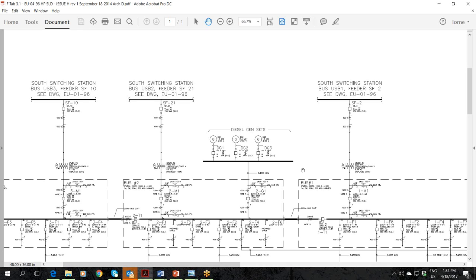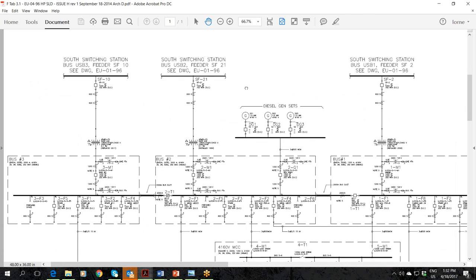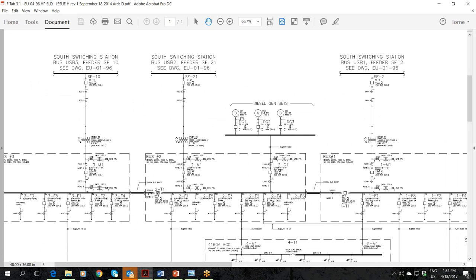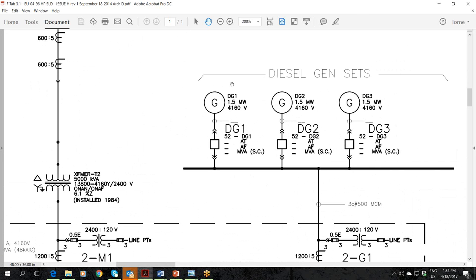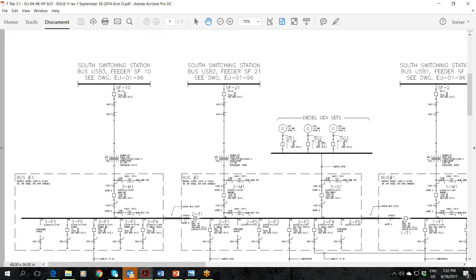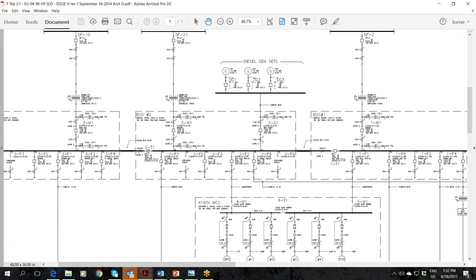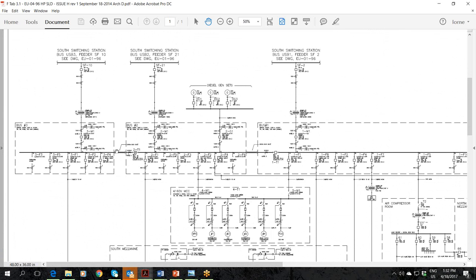The heating plant is quite different in terms of its architecture. We've got, again, 3 breakers from the south switching station, 1 from each of the 3 buses. So again, we've got truly at least 2 supplies here, all the way up to the EPCOR Garneau substation level, giving us lots of flexibility in terms of power flow. We've got 3 diesel generators that are used for black start. These are 1.5 megawatts each, and they live on bus 2. So we've got a 3-bus system.